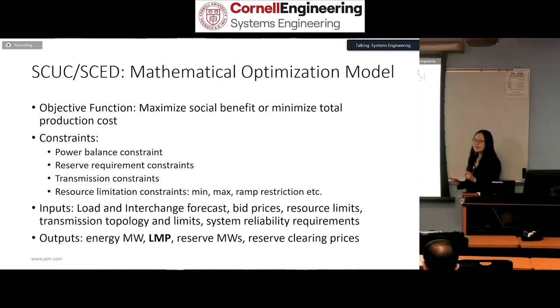So for the state estimate solution for PJM, we run every 1 minute. For contingency analysis at PJM, we run every 3 minutes. So all this latest information will be fed to the SCED, which runs for real time SCED, every 3 minutes. So we want to make sure, with all this latest information, we'll send out a dispatch signal to all generators, with a signal every 5 minutes.